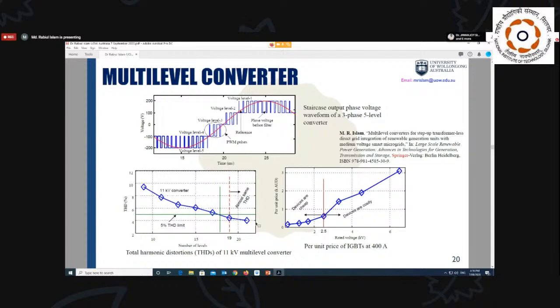And by increasing the number of levels, we can decrease the harmonic components. For example, for an 11 kilovolt converter, if we use around a 17-level inverter, then the output voltage harmonic content would be less than 5%, which inherently satisfies the IEEE standard. That means we can feed that power to the grid directly without using any line filter.